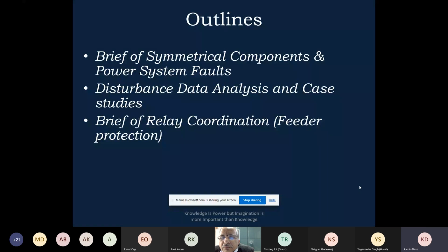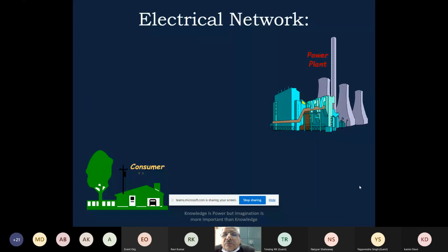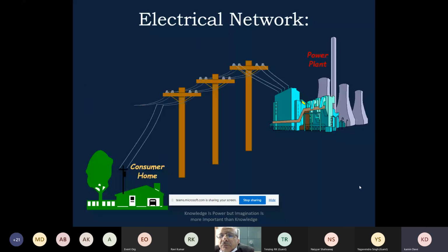Okay, so let us start with some basics: power generation, power transmission, and power distribution. Normally, the power generation is done at 6.6 kV, 11 kV, 13.8 kV, 21 kV, 22 kV, 27 kV voltage levels. Then it is stepped up for bulk transmission to 220 kV, 400 kV, and then further stepped down to sub-transmission at 132 kV, 66 kV, 33 kV, and to the distribution level at 11 kV, 6.6 kV, 440 volt, 230 volt.